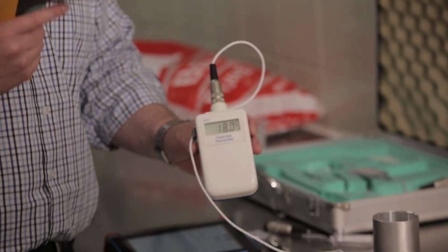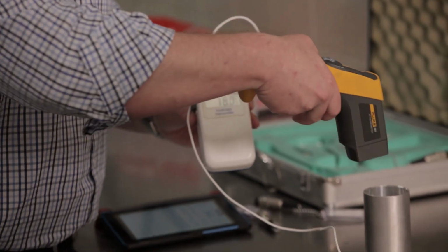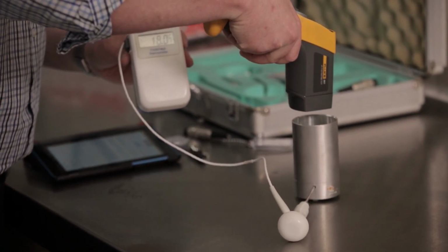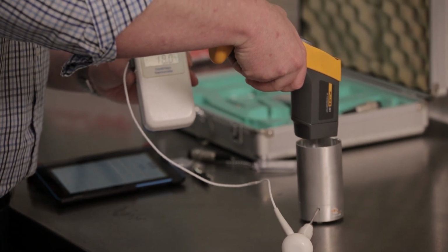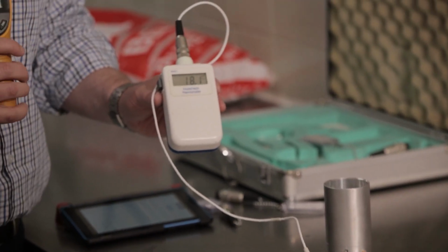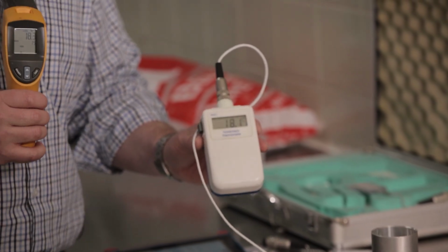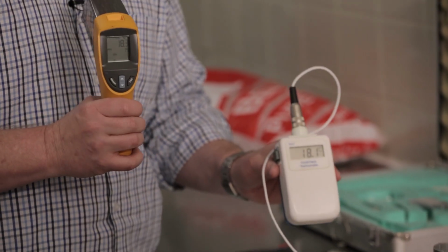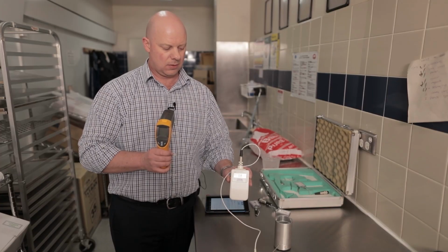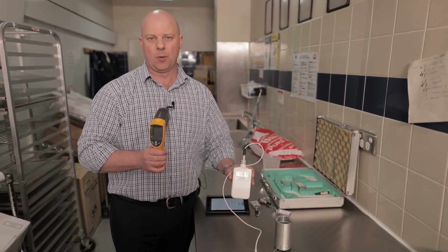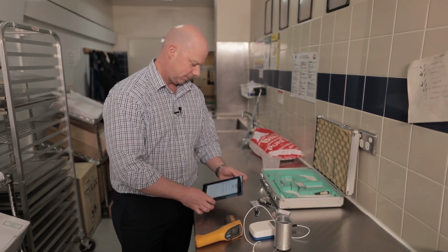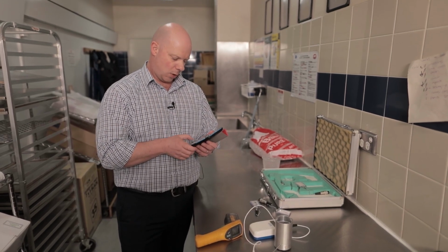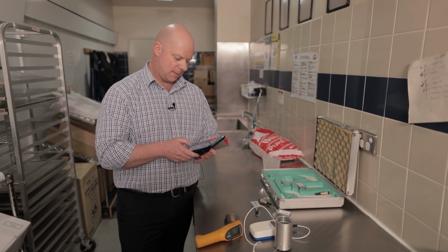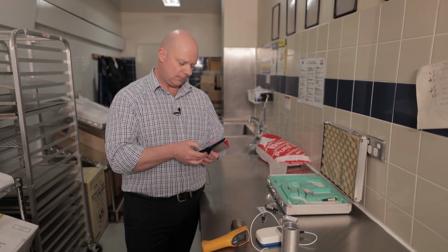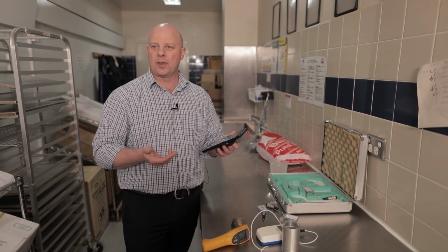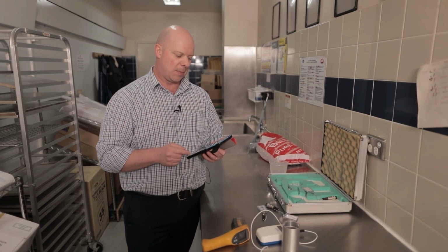Once that stops moving, then we want to do our IR gun, and we point it into the centre of the comparator pot, and we want to make sure that the gun is telling us that it's within plus or minus 1 degree of the digital probe. So we're sitting at 18.1 degrees, the gun's telling me 18.3 degrees, so that means that all of our equipment is accurate. We want to then put that into the tablet, the digital probe at 18.1, the IR temperature gun at 18.3. The tablet tells us that that's okay, it's within the limits, so therefore we can sign that off and we can submit the log sheet.